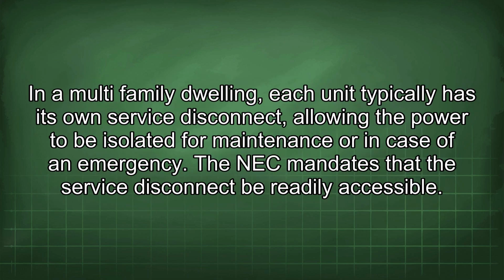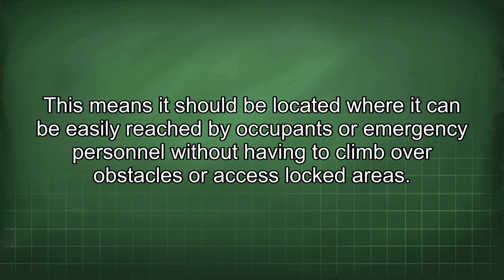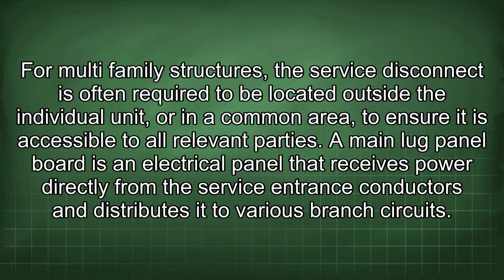In a multi-family dwelling, each unit typically has its own service disconnect, allowing the power to be isolated for maintenance or in case of an emergency. The NEC mandates that the service disconnect be readily accessible. This means it should be located where it can be easily reached by occupants or emergency personnel without having to climb over obstacles or access locked areas. For multi-family structures, the service disconnect is often required to be located outside the individual unit or in a common area to ensure it is accessible to all relevant parties.